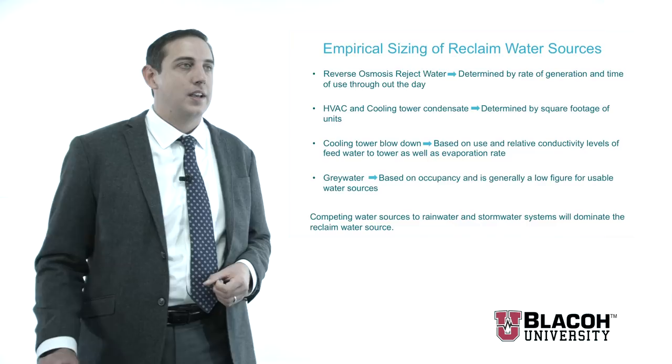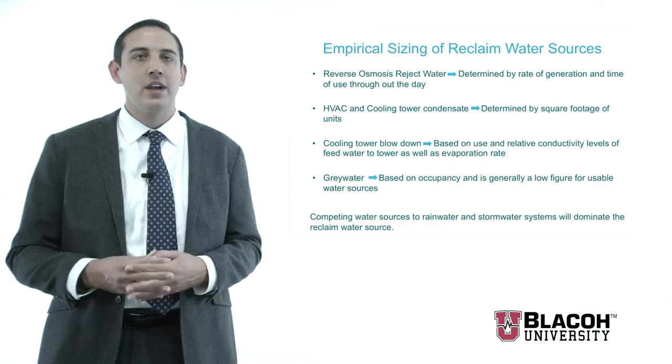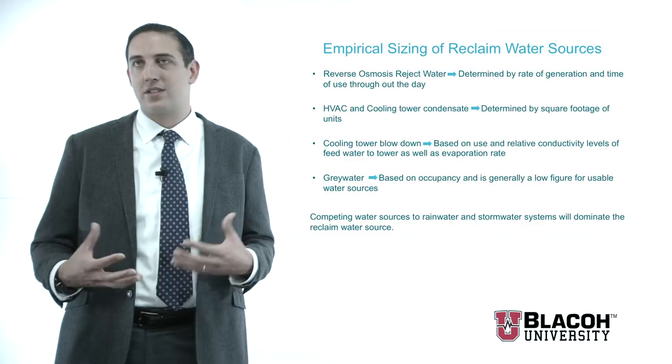For other reclaimed water sources such as reverse osmosis, HVAC and cooling tower condensate, and cooling tower blowdown, these systems are designed based on empirical data — how large your cooling tower is, what the flow rate of your reverse osmosis system is. This also includes devices like dialysis machines in hospitals as a source of reverse osmosis reject water. Reverse osmosis and HVAC and cooling tower condensate are generally classified as clear water systems. Cooling tower blowdown is classified predominantly as more of a gray water source.